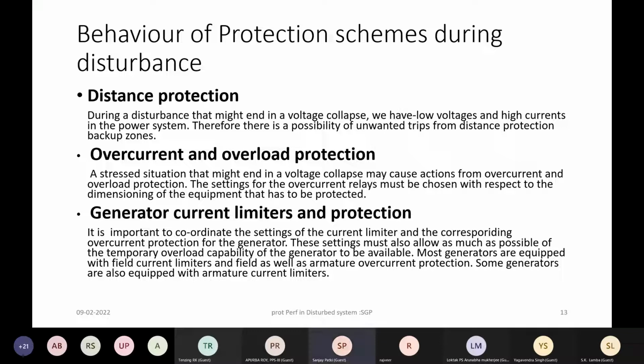Similarly, generator current limiters, stator current limiters, over-excitation limiters, under-excitation limiters, and those settings have to be coordinated with the generator protection and other protection schemes, so that the limiters provided in the AVR should act as a first line of defense before the protection is called upon to operate. That is basically the coordination between the excitation system limiters with respect to the protective relays.